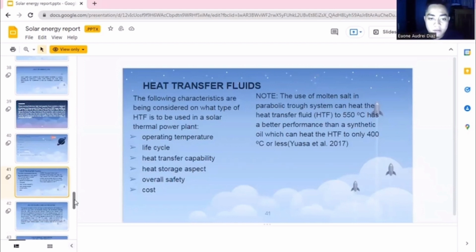Heat transfer fluid. The following characteristics are considered when determining what type of HTF is to be used in a solar thermal power plant: first, operating temperature; second, life cycle; heat transfer capacity; heat storage aspect; overall safety; and cost. Note that the use of molten salt in a parabolic trough system can heat the HTF to 550 degrees Celsius, which has better performance than synthetic oil, which can heat the HTF to only 400 degrees Celsius or less.